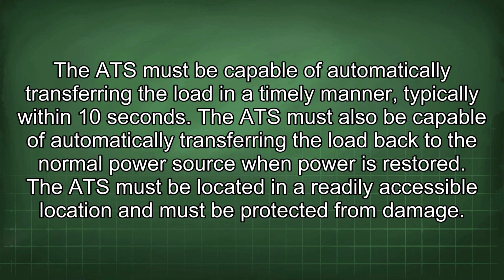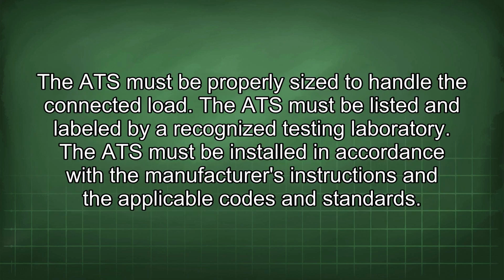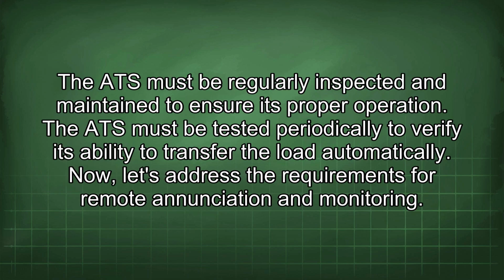power is restored. The ATS must be located in a readily accessible location and must be protected from damage. The ATS must be properly sized to handle the connected load. The ATS must be listed and labeled by a recognized testing laboratory. The ATS must be installed in accordance with the manufacturer's instructions and the applicable codes and standards. The ATS must be regularly inspected and maintained to ensure its proper operation. The ATS must be tested periodically to verify its ability to transfer the load automatically.